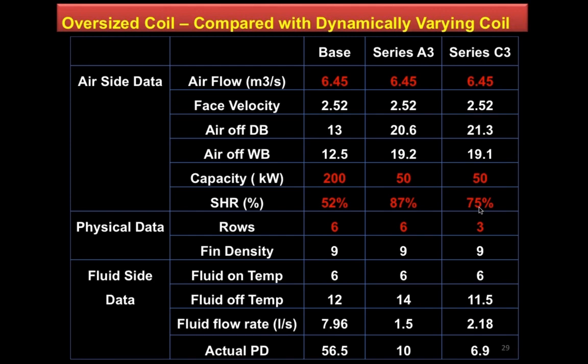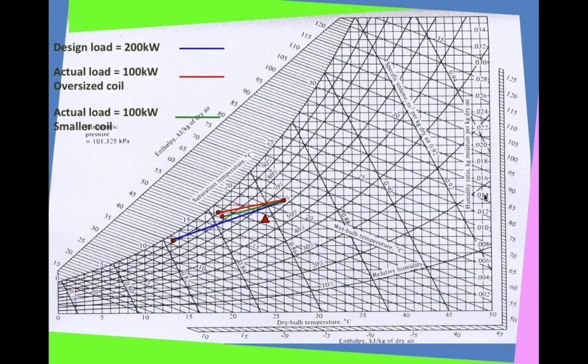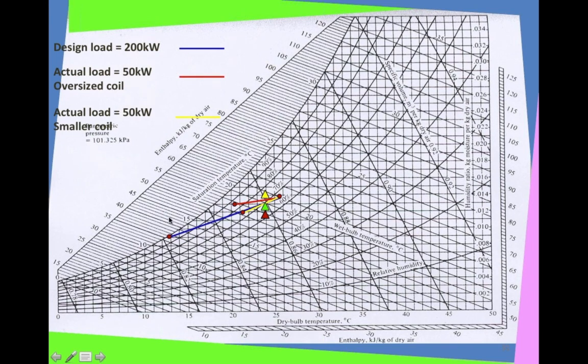better dehumidifying performance. So here I'm going to take you through, in terms of psychrometrics of it, the dark blue line is my oversized coil, 200 kilowatts. The red line is the one that I force my oversized coil to deliver as a 100 kilowatt performance, and the green is when I change that coil size to a smaller coil. Now what happens when I have a part load condition? The blue remains the same, which is my oversized coil.